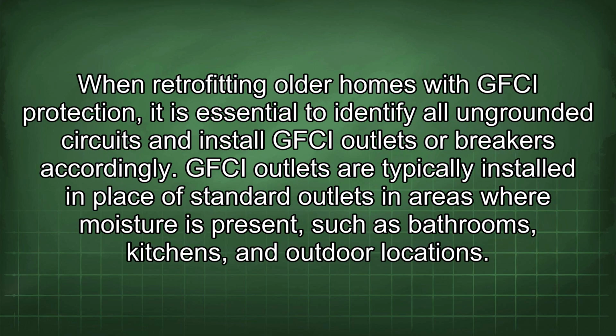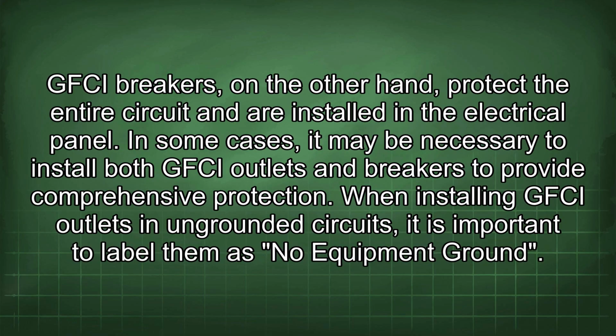When retrofitting older homes with GFCI protection, it is essential to identify all ungrounded circuits and install GFCI outlets or breakers accordingly. GFCI outlets are typically installed in place of standard outlets in areas where moisture is present, such as bathrooms, kitchens, and outdoor locations. GFCI breakers, on the other hand, protect the entire circuit and are installed in the electrical panel. In some cases, it may be necessary to install both GFCI outlets and breakers to provide comprehensive protection.